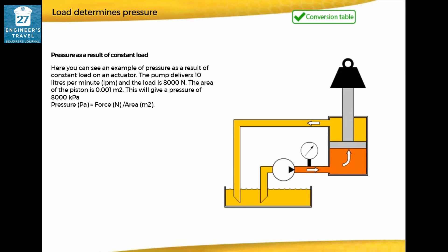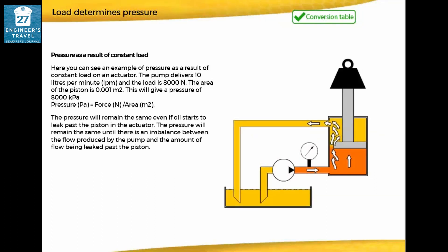Pressure as a result of constant load: the pump delivers 10 liters per minute and the load is 8,000 newtons. The area of the piston is 0.001 square meters, giving a pressure of 8,000 kilopascals. Pressure equals force divided by area. The pressure will remain the same even if oil starts to leak past the piston, until there is an imbalance between the flow produced by the pump and the amount of flow being leaked past the piston.